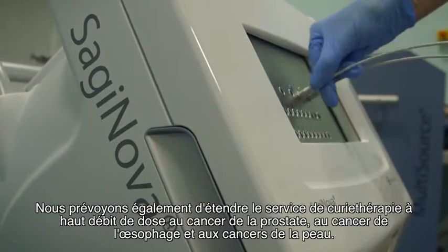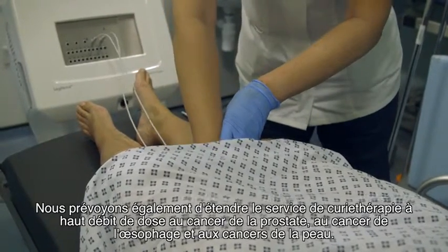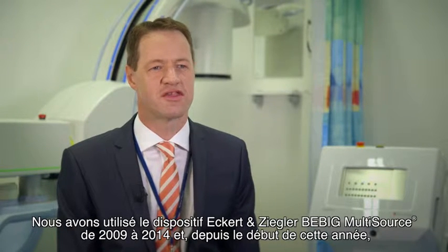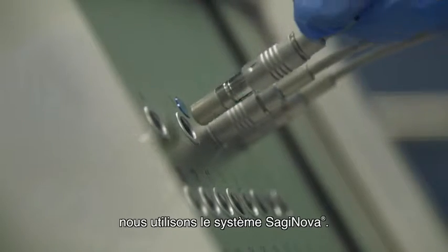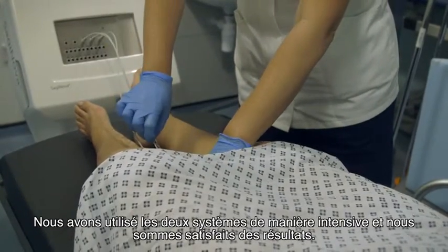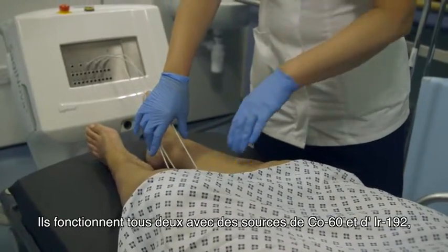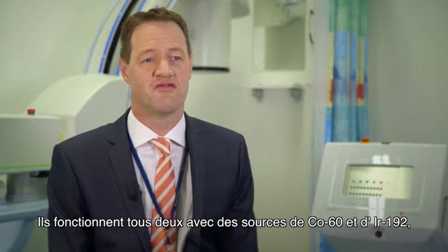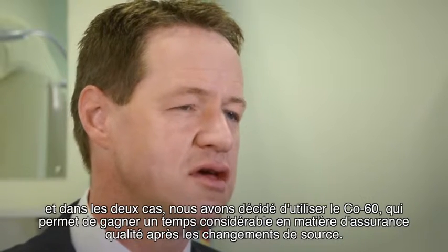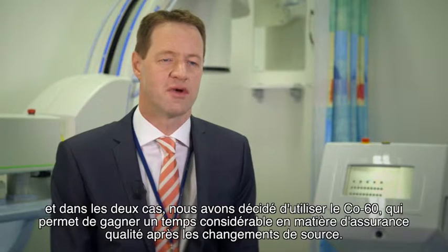There are also plans to expand the HDR brachytherapy service to prostate cancers, esophageal cancer and skin cancers. We have been using the Eckert & Ziegler BEBIG MultiSource since 2009 and for the last year have been using the Saginova system. We have performed comprehensive and extensive commissioning on both systems and were happy with the results. Both systems are available with Cobalt-60 and Iridium-192 sources; in both cases we decided to use Cobalt-60 due to the significant time saving in quality assurance following source exchanges.